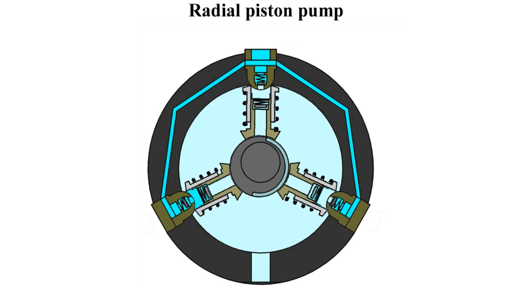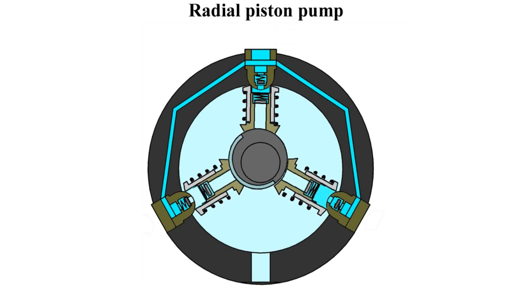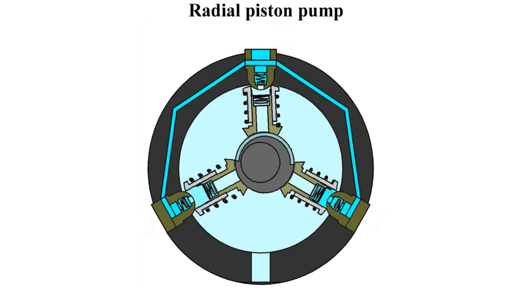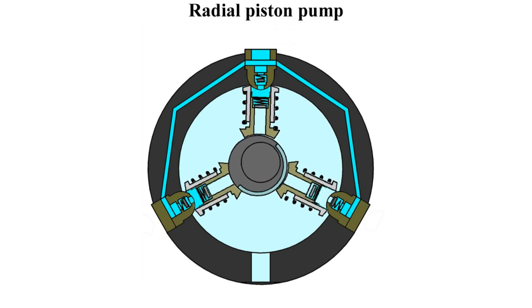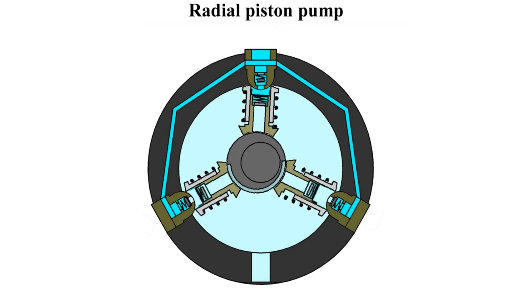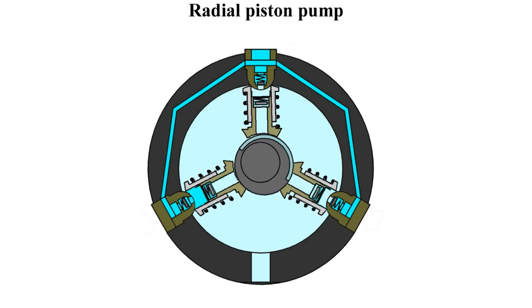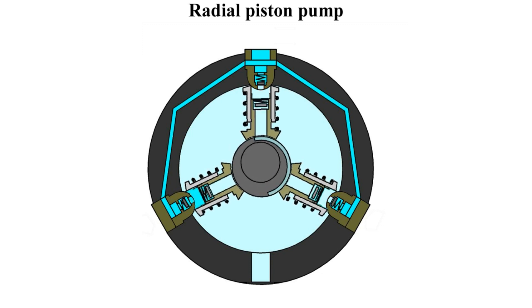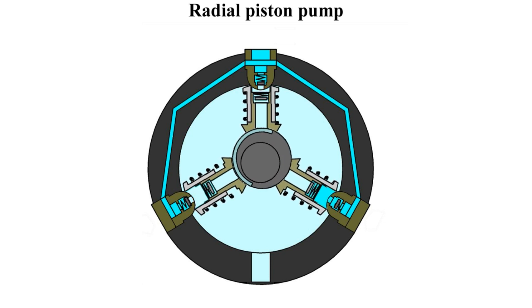When the piston is at the upper idle point, the suction valve and pressure valve are closed. As the shaft rotates, the piston moves in the direction of the center axis of the eccentric. The displacement chamber becomes larger and the suction valve opens due to the negative pressure produced. Fluid flows into the displacement chamber.